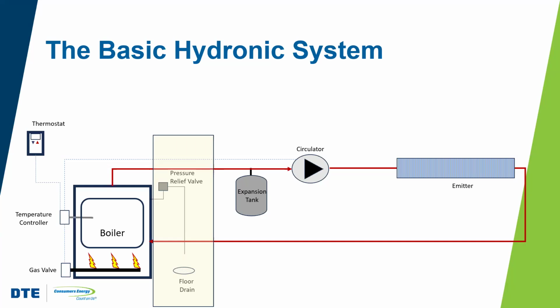The next component to talk about is the pressure relief valve. As that water gets hotter, right, it expands. That's why we've got the expansion tank. As that system pressure increases, it could potentially exceed the pressure rating of some of the components, which would cause a failure. People have said boilers are, and I don't necessarily like saying this, but they're kind of like a bomb, right? They're pressurized systems, so if you had a catastrophic failure, that would be an explosion, right? That's what that would be. And so we want to make sure that we've got a lot of safeties in these systems to prevent that from happening. So we want to make sure that we've got a relief valve that's located close to, if not actually on, the boiler.